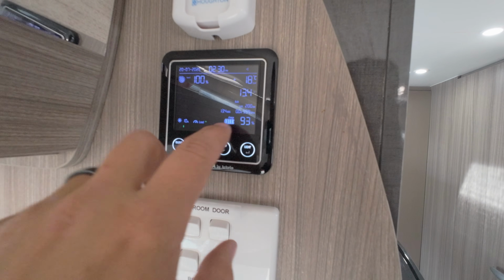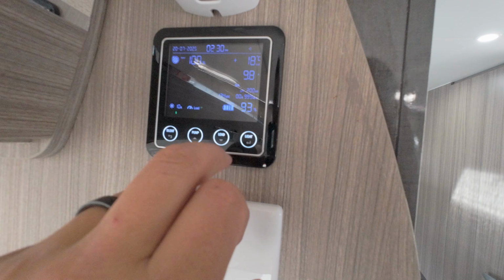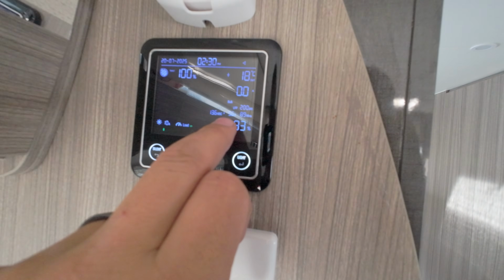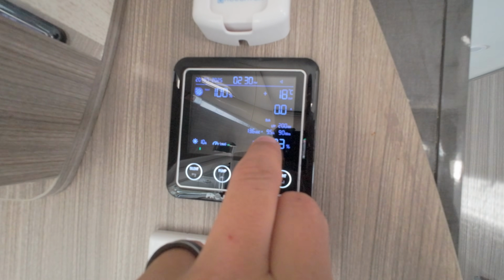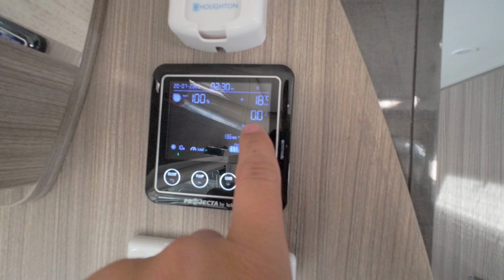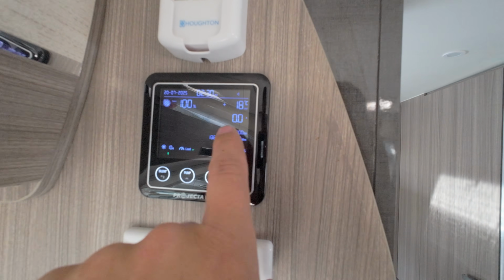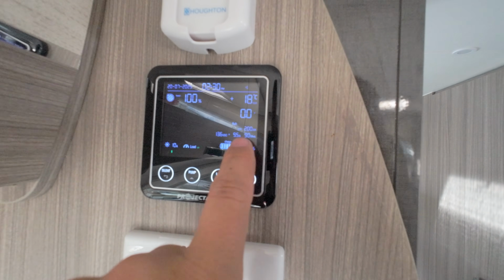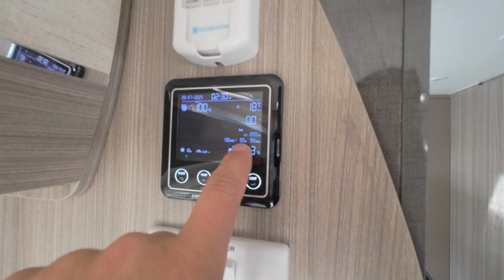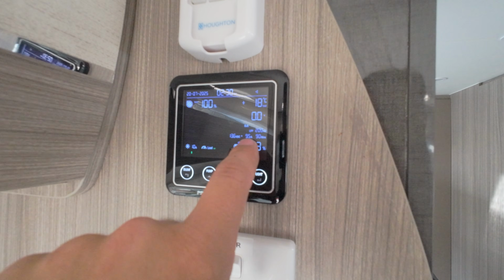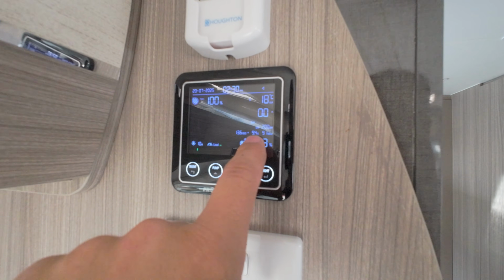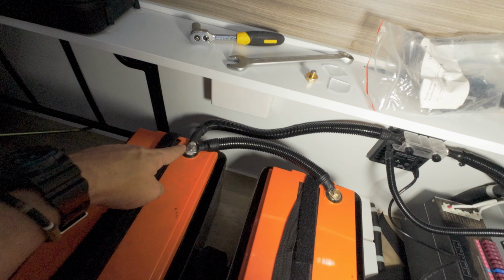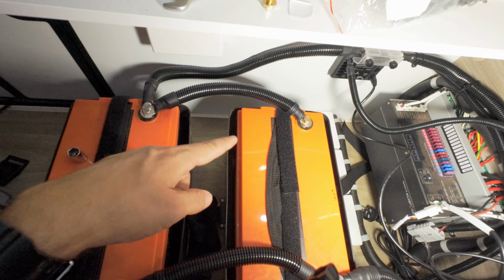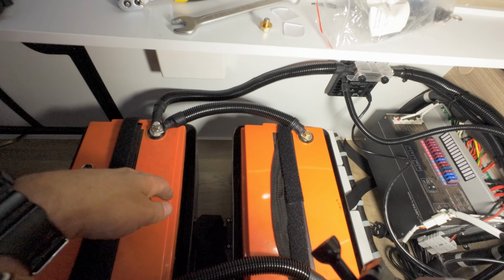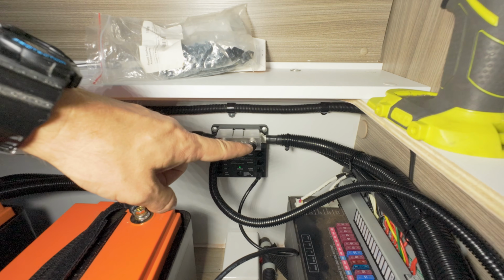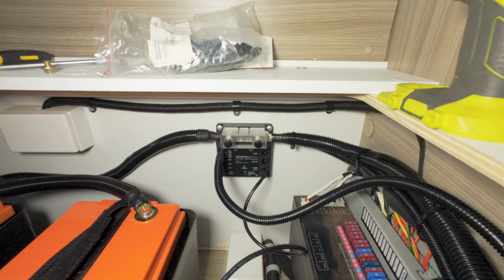So that's a solar input. But then up here, for instance, if I put the load off, you'll see your true battery in and out, because even up here it'll show you current, but that's through the BMS. Down here, along this little line, you'll actually see what your true battery current in or out is measuring at. You need to make sure nothing else is connected to any of the negative terminals on our batteries, because the BMS is using that shunt to measure current in and out.